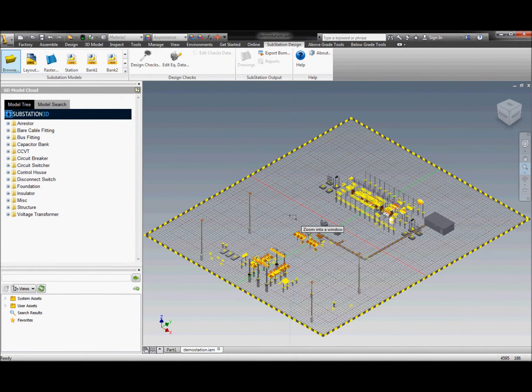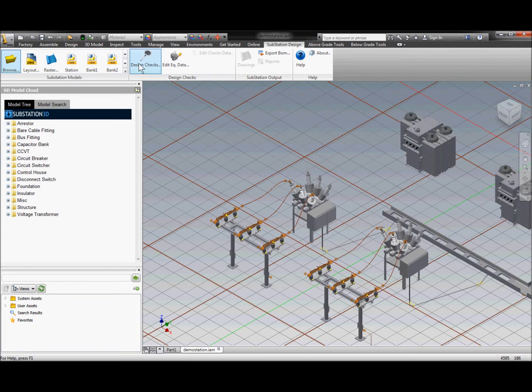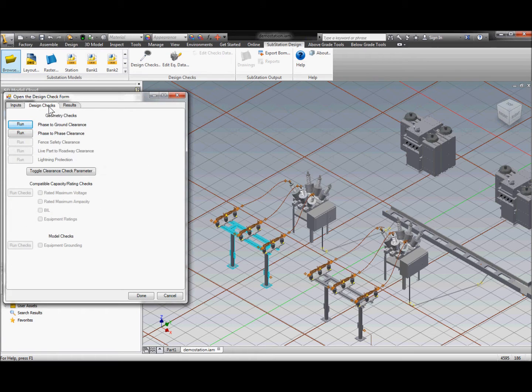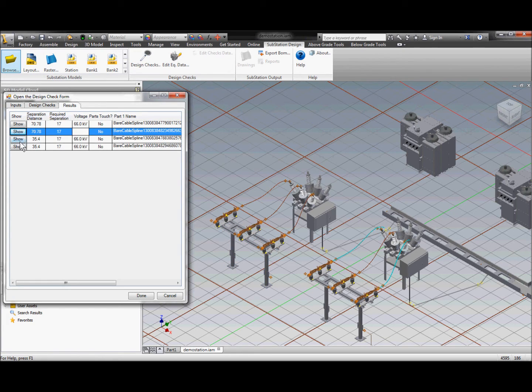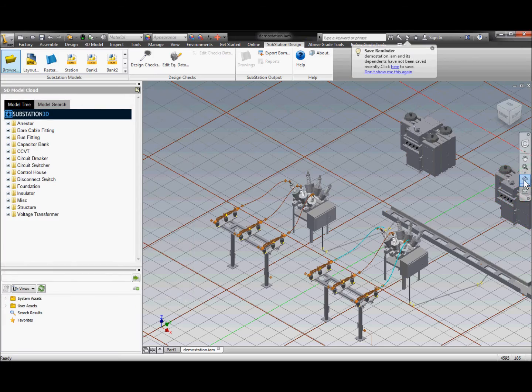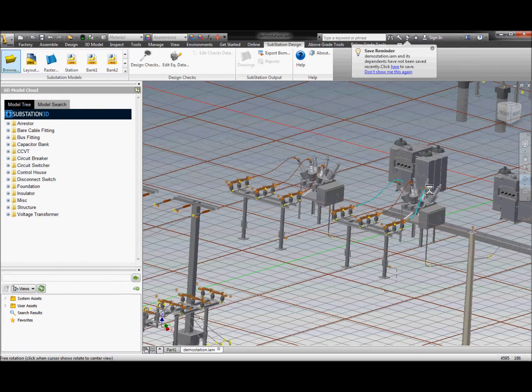The design checking in the substation design tools pulls together all of that information inside the intelligent library — the components as well as the cables, conduit, trench, and all the different pieces come together for design checking. This is where all the work really pays off in the model. We're able to step through ABC phases, look at selected ground structures and ground equipment, and do things like phase-to-phase clearance checking. Preset values are defined in the setup of the substation tools, and the design check will go through and look at required separation values, find out if anything is interfering, and flag any rules breaking those values.